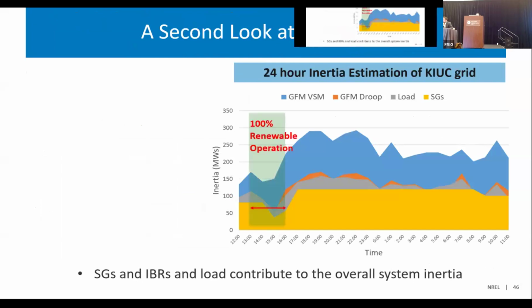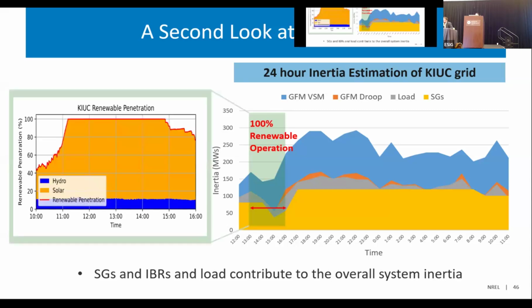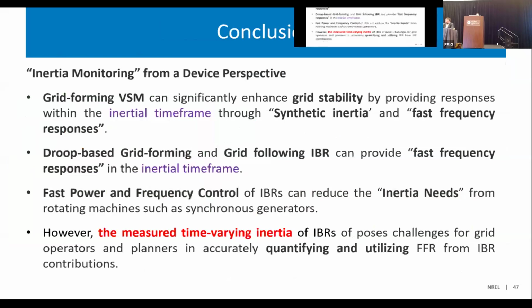Meanwhile, I want to highlight that with the help of the KIUC operators, we intentionally tried to run a 100% renewable operation from 11 a.m. to 3 p.m. This 3-hour 100% renewable operation was supported by both — but you may find a trick here: even while running 100% renewable for this island grid, we were still operating the synchronous generators, but in synchronous condenser mode.